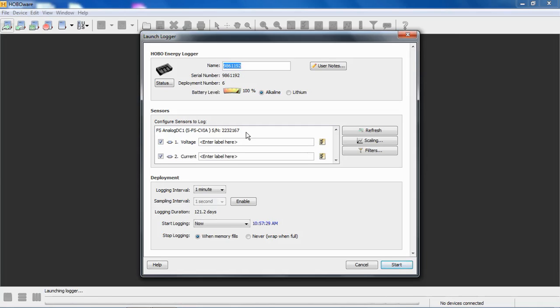It's the same with Smart Sensors, it does it the same way. It doesn't matter what physical connection it has, it's a common bus. So it aligns them by serial number. From the factory, you get the CVIA when you plug it in, one channel says Voltage, the other says Current. These can be configured for either Voltage or Current, it doesn't really matter which channel. So don't be dissuaded by that and say, oh, number one always has to be Voltage, number two always has to be Current. That's not true. They are identical, those module channels.